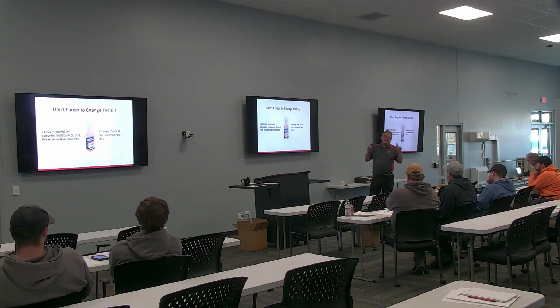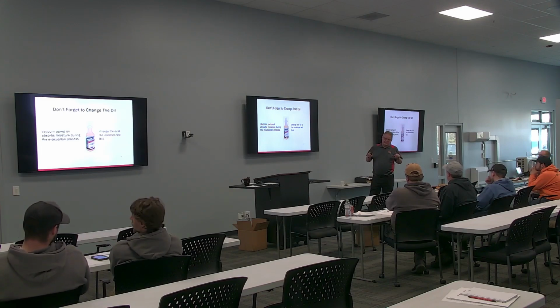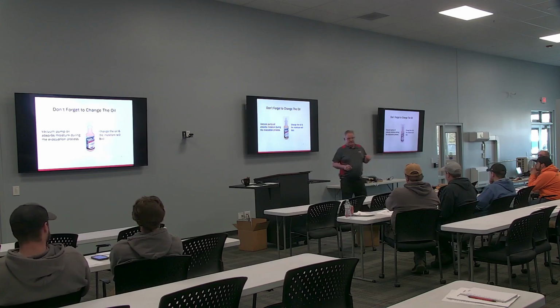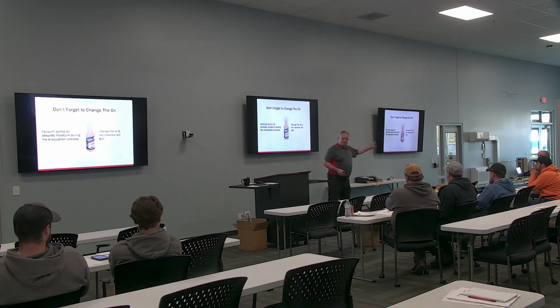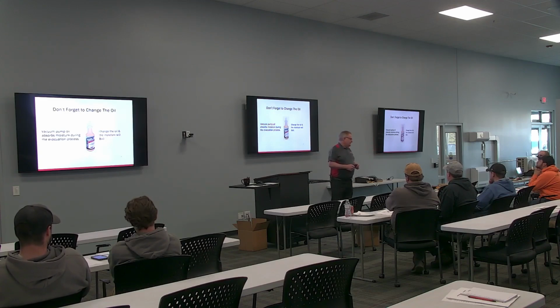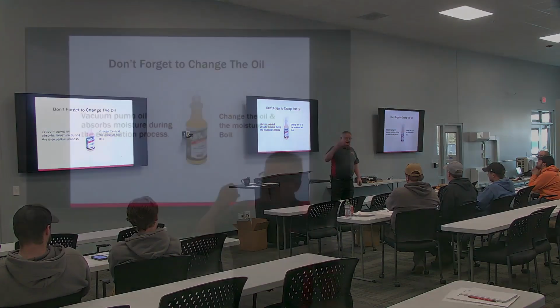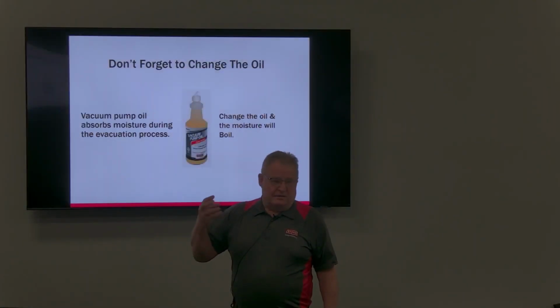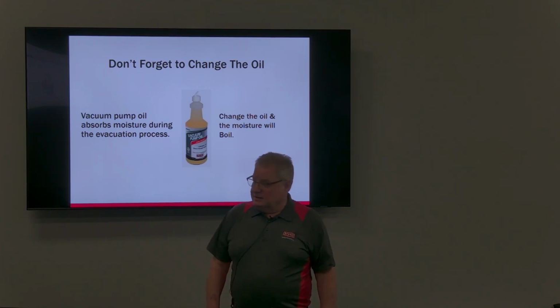Something we've been seeing on mini splits recently. Mini splits do not have filter dryers on them, right? A filter dryer's main job is to dry. It's to absorb moisture. Mini splits can't have them just by their nature. And recently I've had about 4 of them. A guy sends me a picture of oil coming out of the mini split and it's green. It almost looks like dye. That's moisture. Okay, this is moisture in the system.